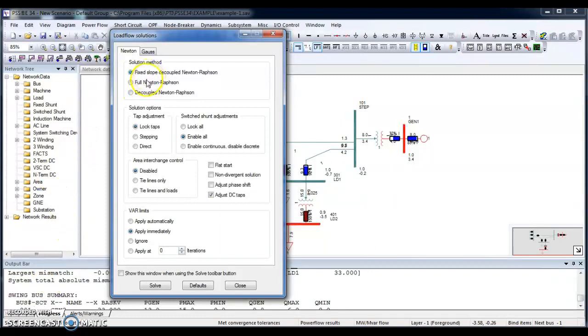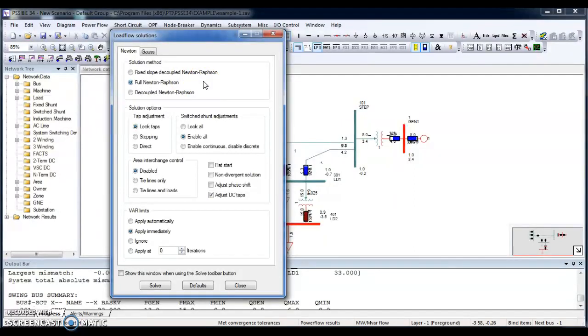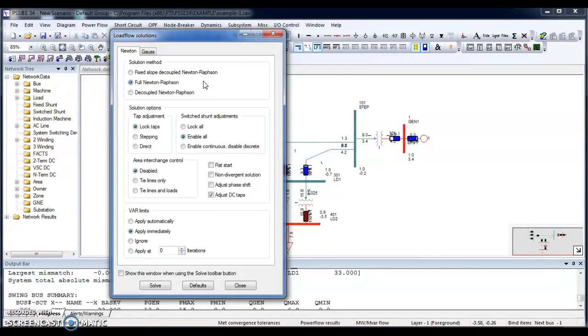If I select full Newton-Raphson, there is an advantage: it is very rapid to converge on well-conditioned cases. But there is a disadvantage like it is intolerant of data errors and voltages, and there is no indication for cause of convergence failure. There must be some difficulty of converging when reactive limits are restrictive in that case.